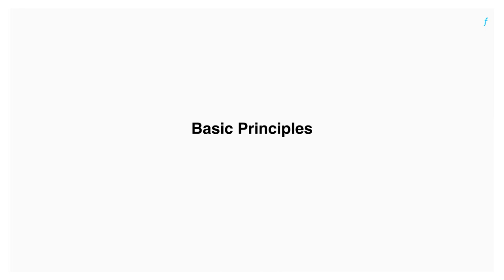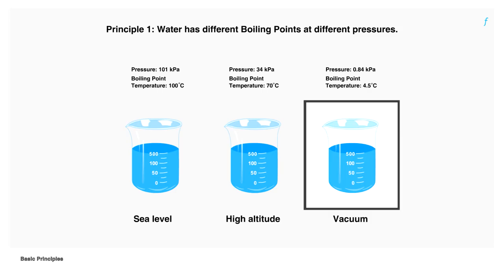Before we learn the working of an absorption chiller, here are three basic principles which we have to understand. Water boils at different temperatures under different pressures. At atmospheric pressure, water boils at 100 degrees Celsius. At lower pressures, it boils at lower temperatures. Following the same principle, at vacuum or at extremely low pressures, water evaporates without any external heat energy input.